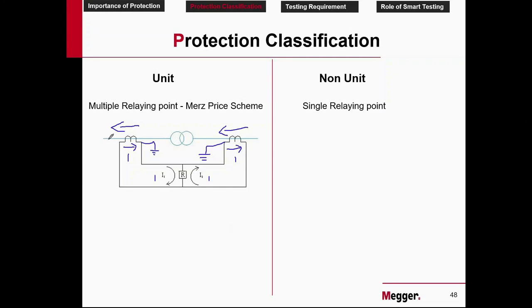Now let's say there is a fault outside. A fault occurs here. Fault at F1. Because of the fault, let us assume that the magnitude increased to 10 amps. Earlier it was 1 amps, now it is 10 amps because of the fault. Now you can see, does the primary current direction change? No, it does not change. It still feeds the fault. If the primary direction does not change, the secondary direction does not change. That means 10 minus 10, it's still 0. The relay reads 0 current, even for a fault. But you can find that the fault is outside the CT. Therefore, the relay does not read any fault current.